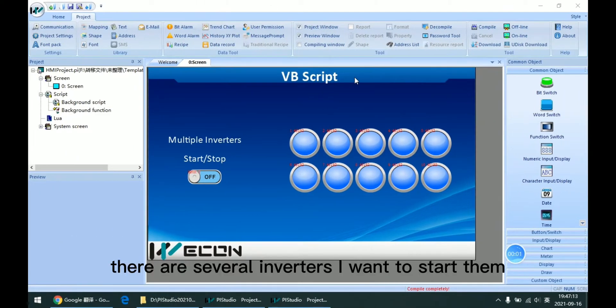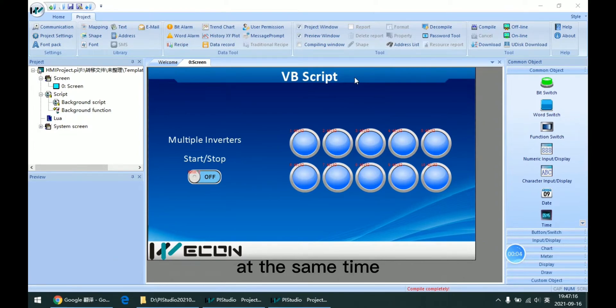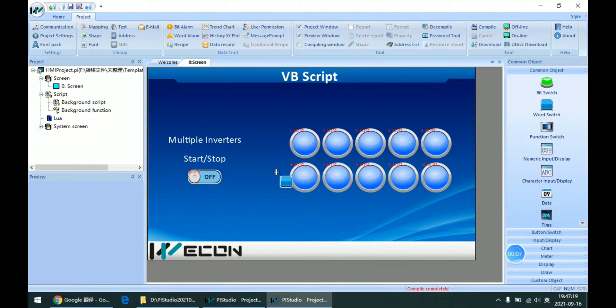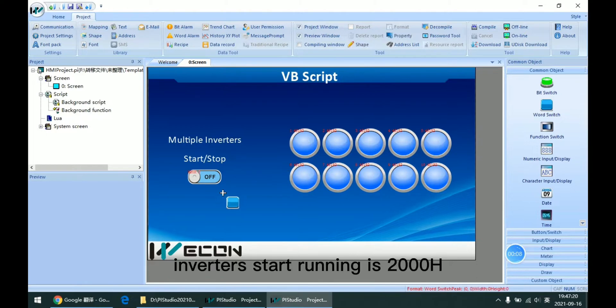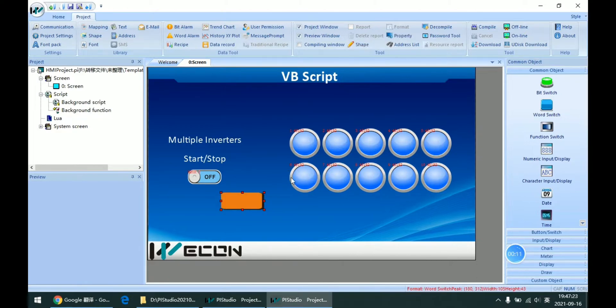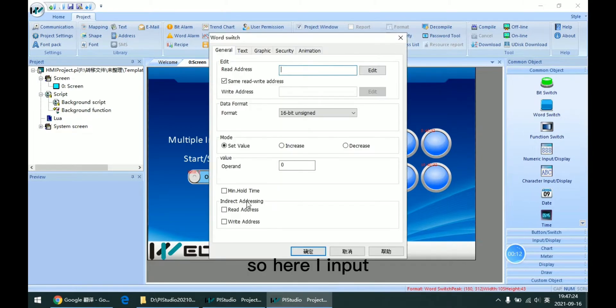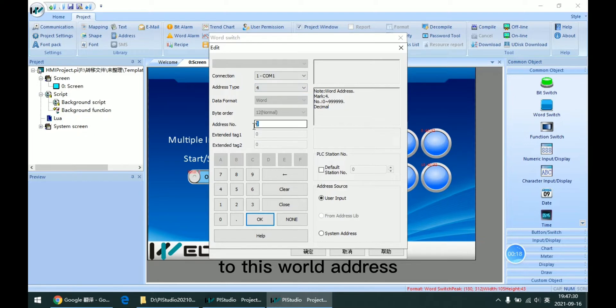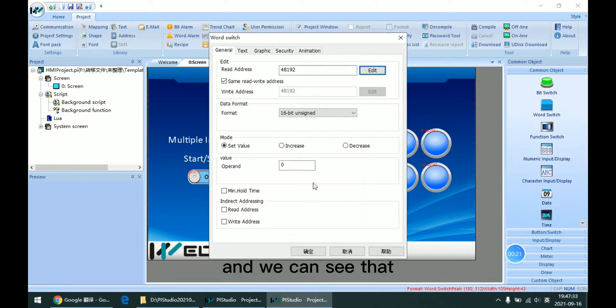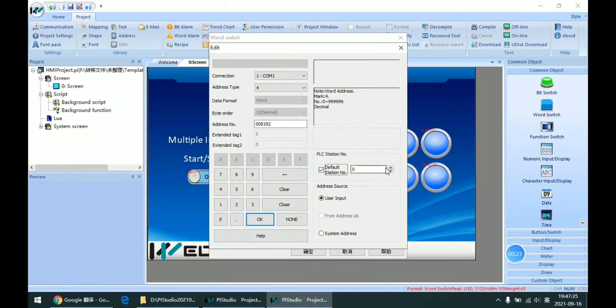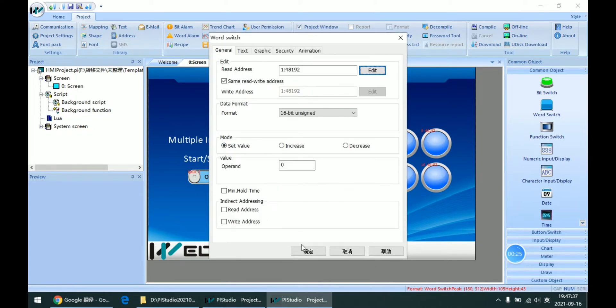For example, there are several inverters I want to start at the same time. As we already know, the inverter start running is 2000 hex. So here I input the 8192 to this word address. And we can see that this is set to the value 1.